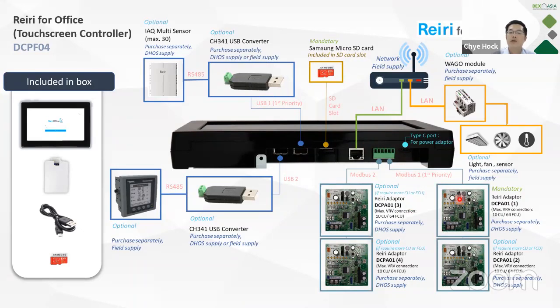You need to connect to the Reiri adapter, which will be mounted inside our VRV condensing unit, up to a maximum of 10 CU systems, and 64 fan coils can be connected under one card. In case you have more than 10 CU systems and 64 fan coil units, we can add multiple cards to both Modbus ports, depending on your quantity of systems, fan coils, and CUs.